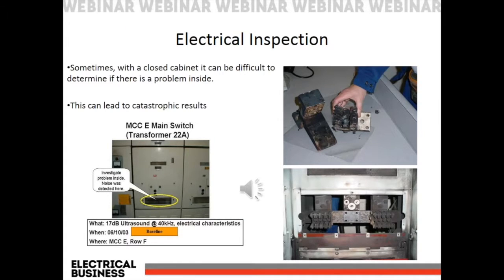There's a couple case studies showing up here. There's one we have that's an MCC, and with it being enclosed, it's hard to determine something. People say to me, well, I can get IR windows. You can, and they're great technology. We know a lot of IR companies and IR window manufacturers who actually make ultrasonic windows as well. But at the same time, if you don't have those windows, you can't use them. You can't diagnose unless you open up the panel. So with a closed cabinet, it can be difficult to determine if there's a problem inside, and that can lead to catastrophic problems. But what we're able to do is scan, and you can see in the diagram on the left that we were able to scan through the air vent there, and this is what we heard inside this particular MCC.